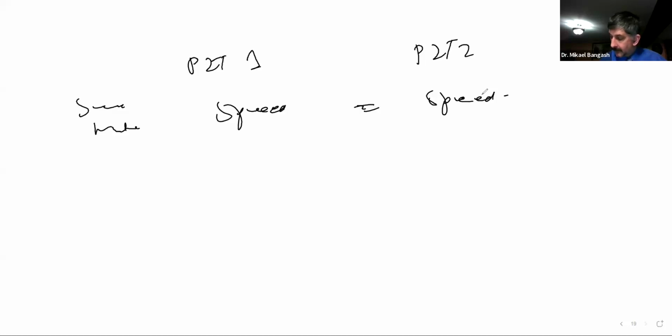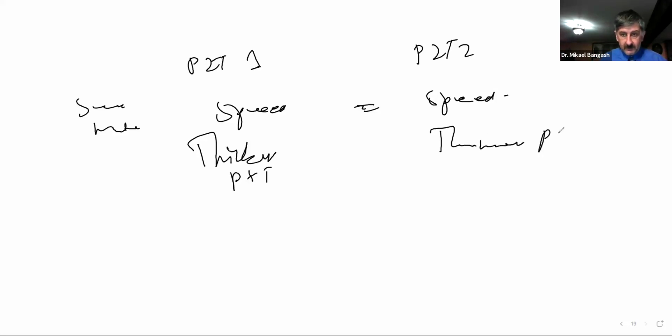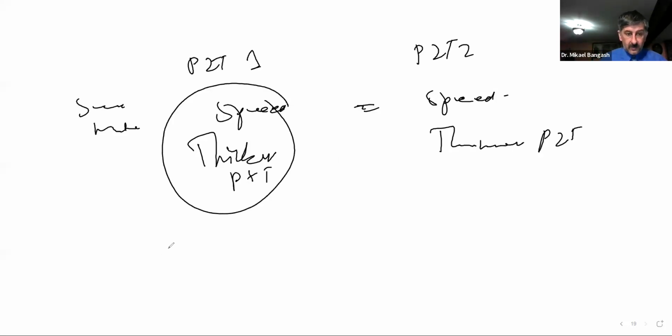Now the thicker crystal will make a continuous wave transducer with a lower frequency. So let's say this one has a thicker PZT and this one has a thinner PZT. Would this make it a continuous wave transducer with a greater frequency? I'm sorry, even lower frequency, sorry.